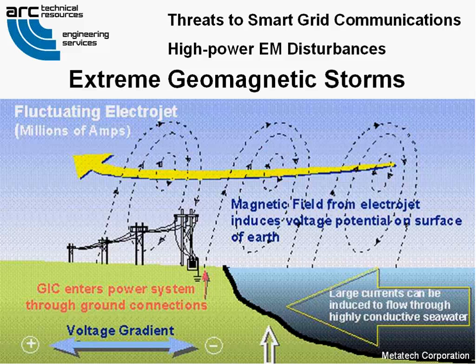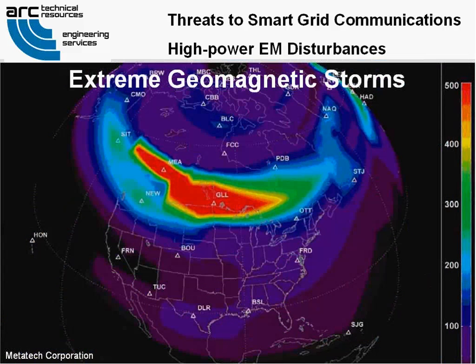Millions of amperes of current can flow through highly conductive seawater, and the fields induce large voltage potential differences onto the surface of the Earth. The resulting quasi-DC voltage gradients force large ground-induced currents into the power system through its ground connections. Then comes the fried transformer as a result. These effects can lead to voltage collapse of the power grid, as experienced in Quebec on March 13th of 1989.